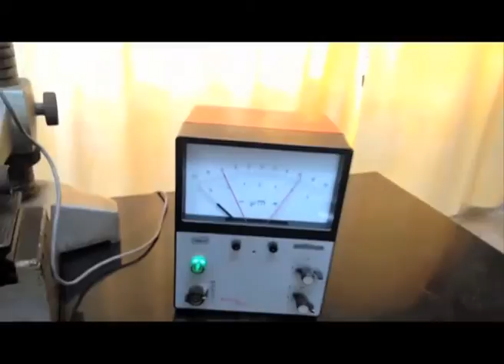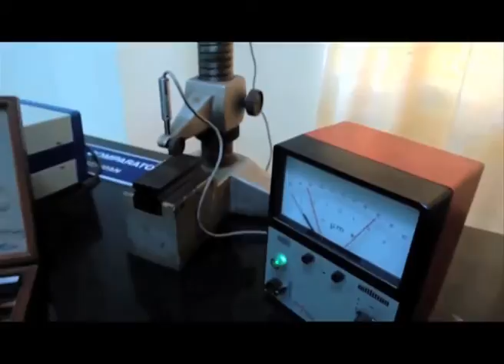We can connect two comparators at a time, A and B, and this knob is for adjusting the sensitivity of the comparator. Now it is set to 100 units, 100 microns. The highest sensitivity is 0 to 3 microns. Now you can see the knob is set to 100 microns. So the range is from 3 microns to 1000 microns.